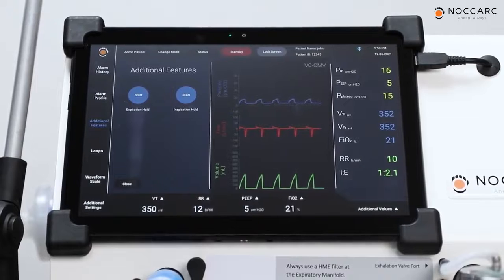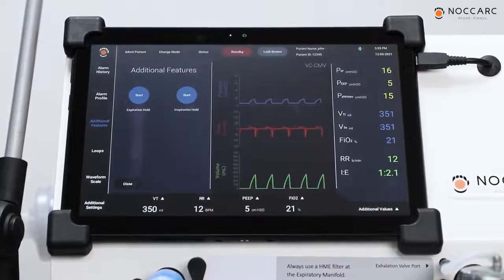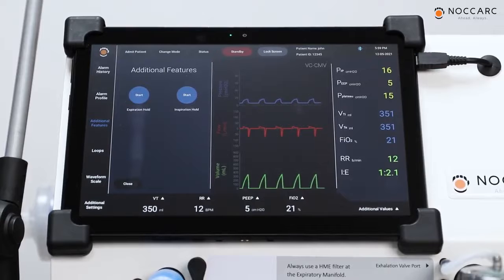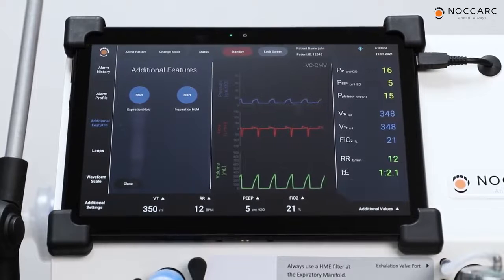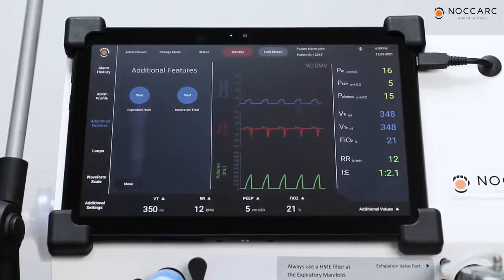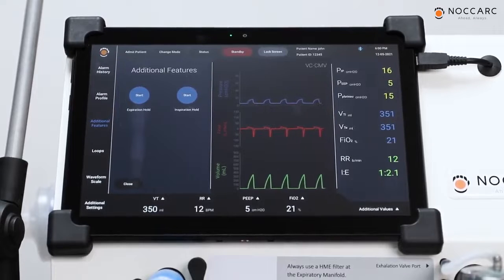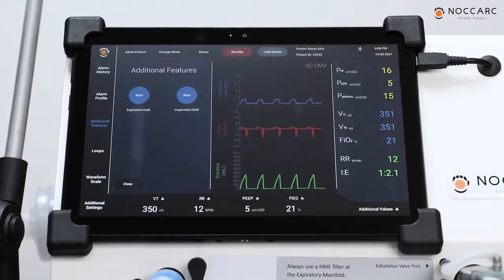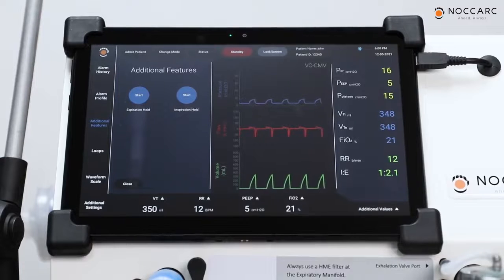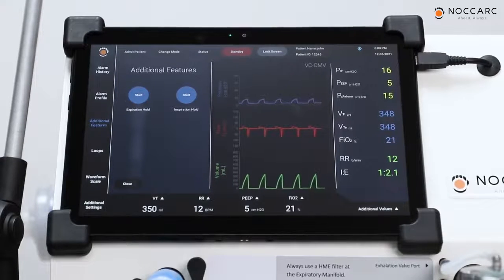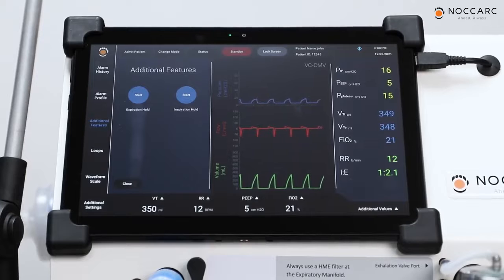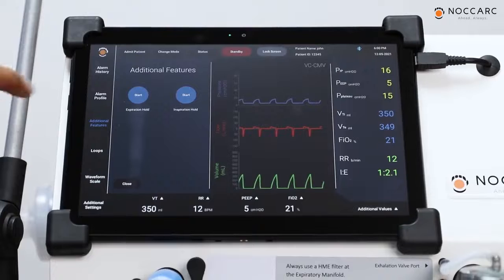Expiration hold extends the expiratory phase of the current breath for the purpose of measuring intrinsic positive end expiratory pressure. It has no effect on the inspiratory phase of the breath. During the expiration hold, the pressure on either side of the artificial airway is allowed to equilibrate, which determines the pressure during no flow state. To perform expiration hold, press on start.